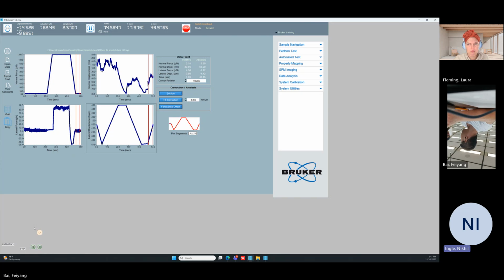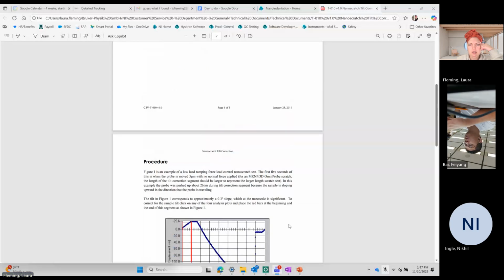I think we can try a scratch test on a quartz sample. I would not. You can, but I would not. You're going to blunt the probe. Quartz is pretty hard. You're welcome to try that. It's just that you're not really looking for data right now on the fused quartz, and so you're doing really nothing but risking your probe. If you put in too high of a force, and we don't know what a good force is, you run the risk of causing blunting.